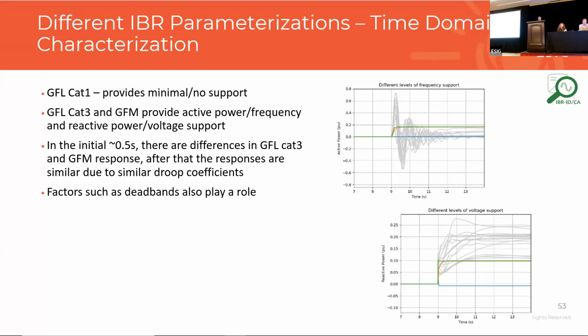All of this capability that we have identified is essentially viewed at the transmission point of interconnection, because that's where the jurisdiction of the system operator starts from. But an inverter-based resource like category 1, which is essentially doing fixed power operation, controls fixed power at its turbine level, at its inverter level. So if you have a voltage event that occurs on the transmission bus, and you have a resource some impedance away which is keeping Q fixed, the remaining inductive elements across the network have to get some reactive power supply through it, and they draw that from the network.